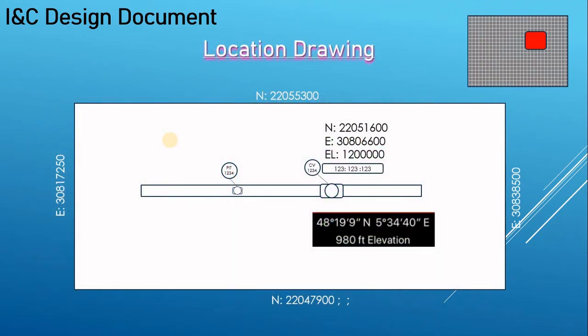From the 3D model, another thing that comes out of it is the location drawing. The location drawing is where you can see where all your instruments, inline and offline transmitters are. The way we do it is that in the 3D model we take a block, or a cube or something, and from the database we can actually create those drawings.